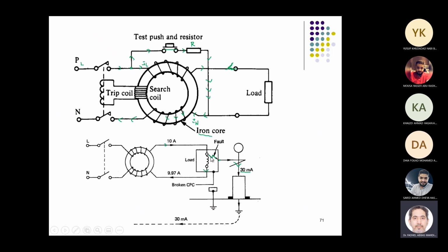It only operates when you have a leakage, a fault that goes through a human body or through the body of the device to ground. So when you have a leakage of current, part of the line current goes to ground, for example, or part of it goes to the neutral. So when there is a difference of, let's say, at least 30 milliampere for 30 milliampere sensitive devices, this device will trip. So the line current flux will be different from the neutral current flux because the currents are different. As a result, the net flux will not be zero. That will induce a voltage here that will trip the coil. This is the principle, like a differential, but this is not a differential.